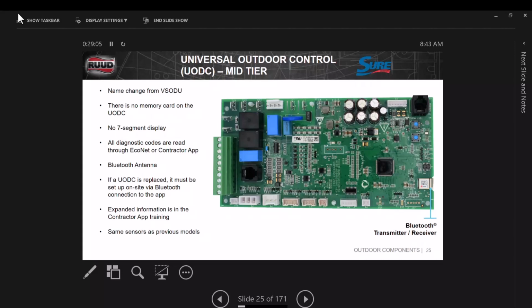If this board is ever replaced, it must be set up via Bluetooth. That's what I was telling you a little bit before. You put the model and serial number of the unit in there, and it takes all the information that needs to be in that board for that particular unit and loads it in. And that would be like fan motor speeds, what tonnage the unit is, all that would be loaded in there. More expanded information on that is in the contractor app. It will walk you through doing it.